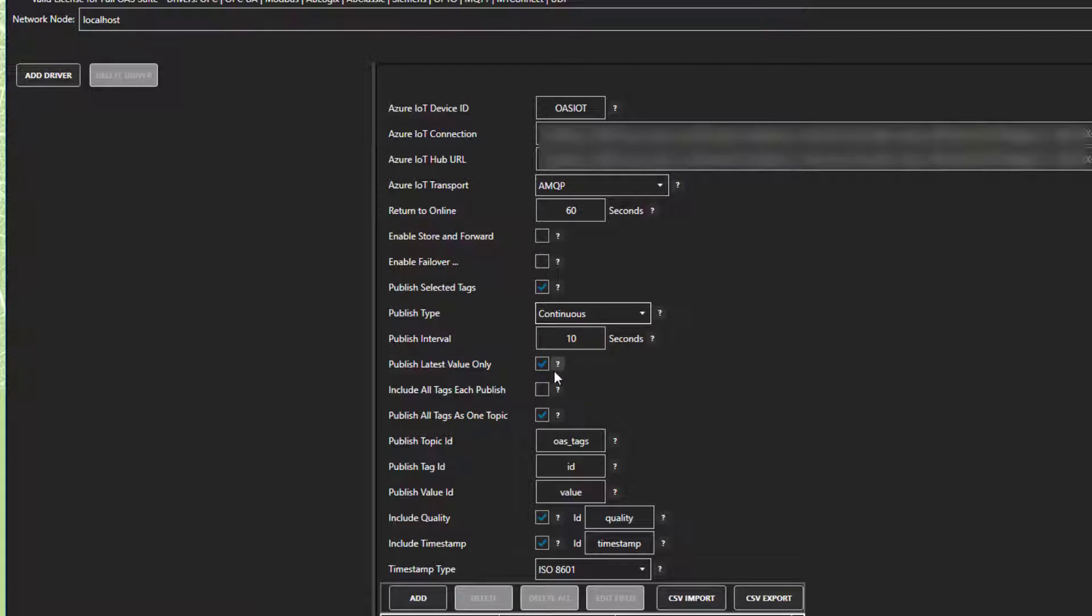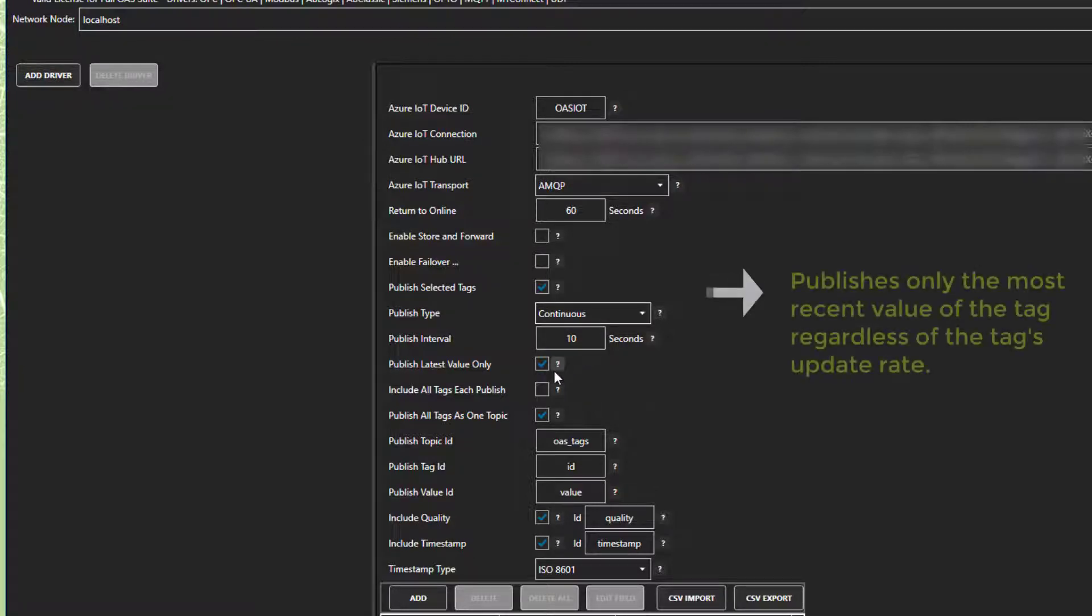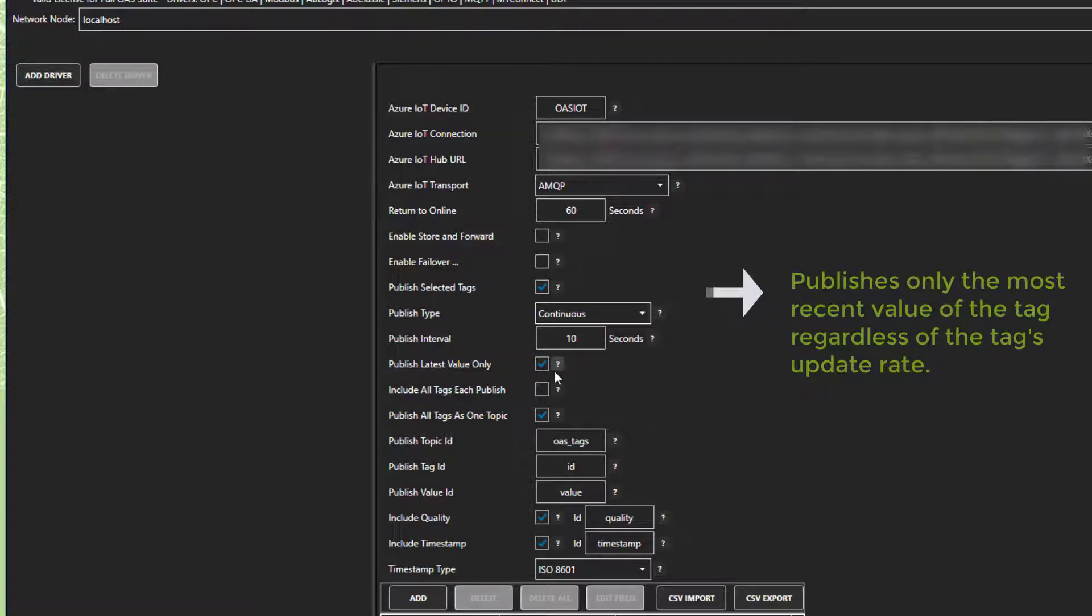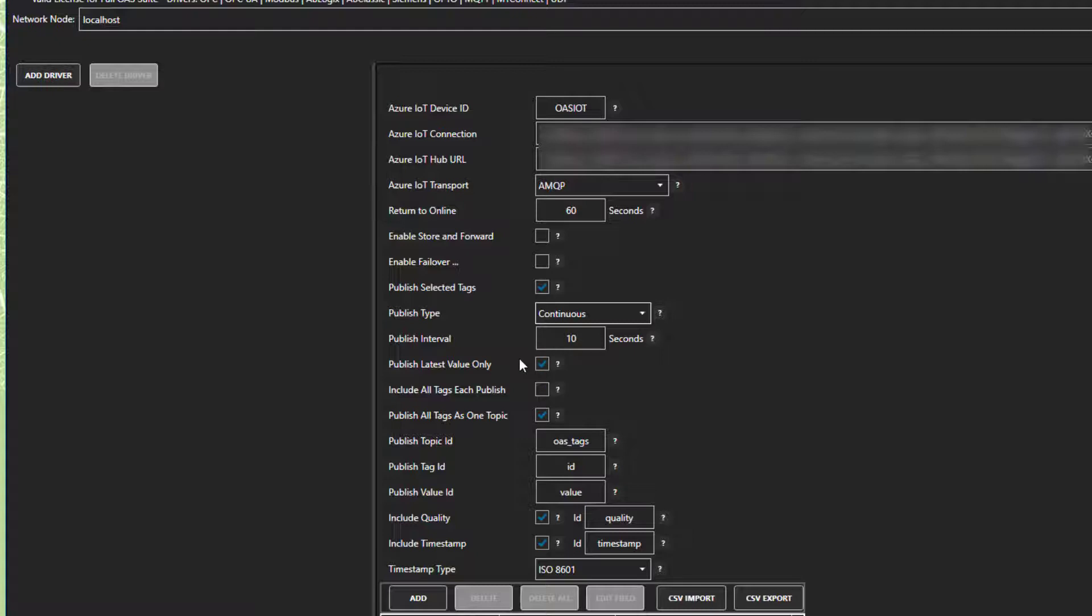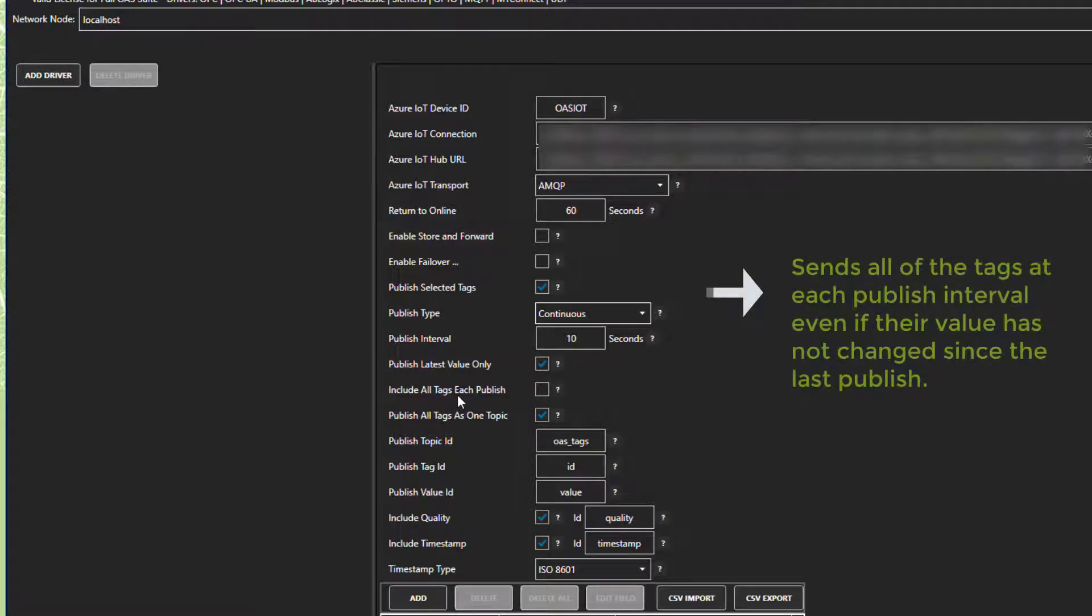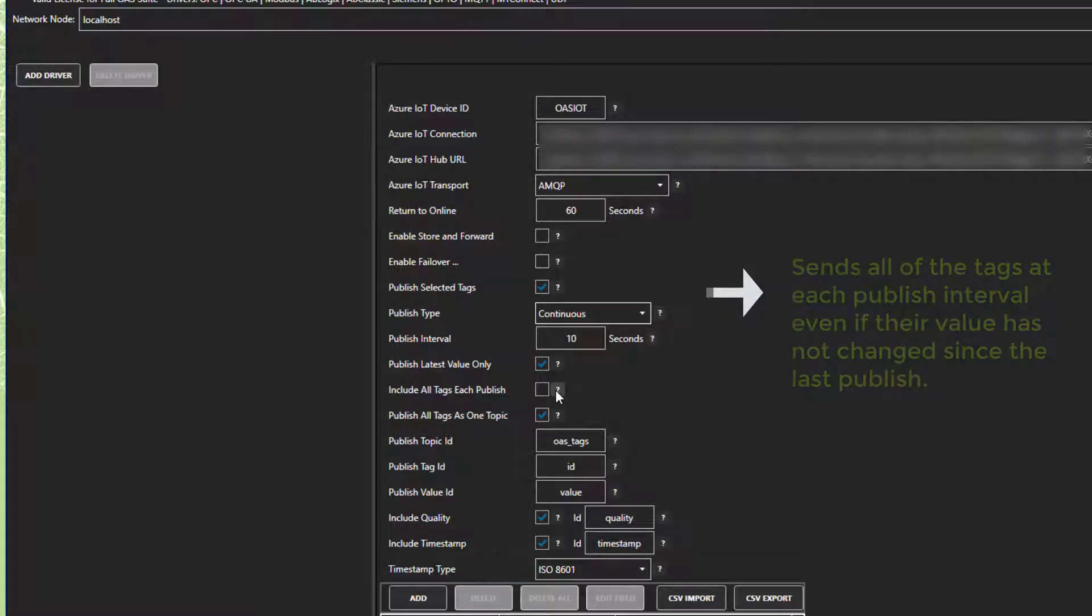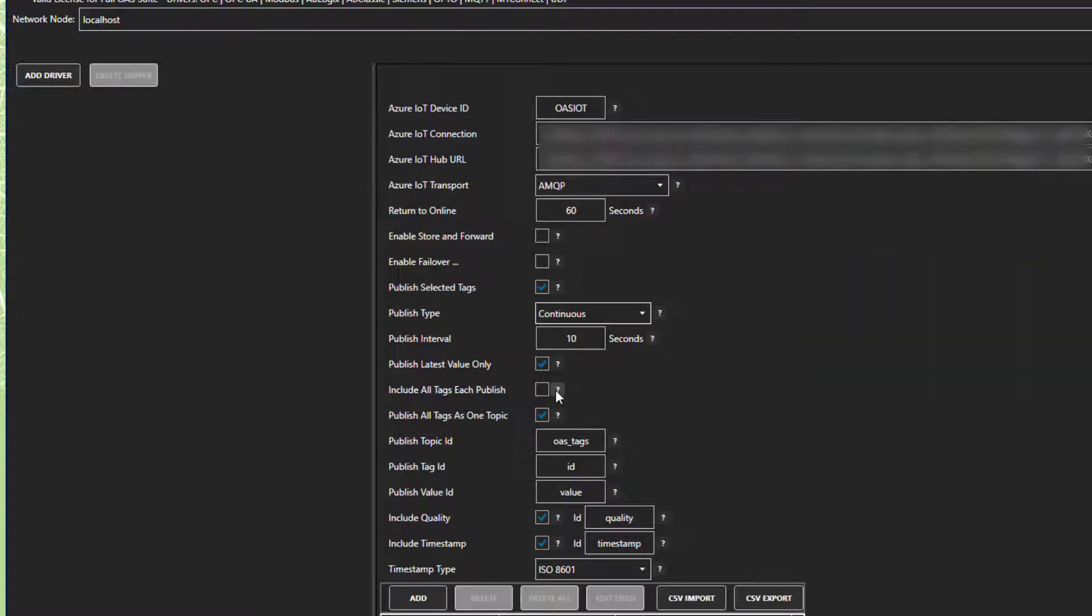Let's look at the checkboxes here. Publish Latest Value Only, when checked, will publish only the most recent value of the tag, even if the update rate for the tag is faster than the publish interval. So if your tag has changed its value five times during the 10-second publish interval, it will only send one value, the latest. If we uncheck it, it will send all of the values of the tag since the last publish. Include all tags in each publish. If this is checked, it will send all of the tags at each publish interval, regardless of whether or not they have changed values. Unchecked, it will publish only tags that have changed value.